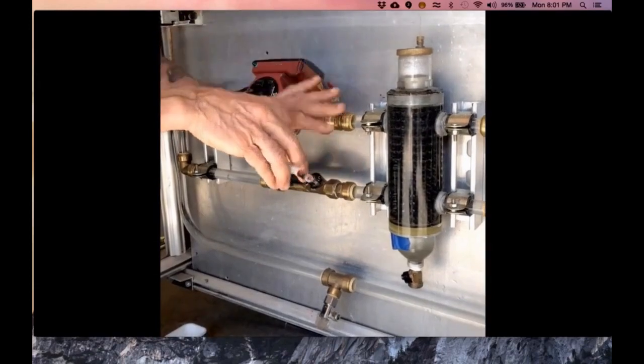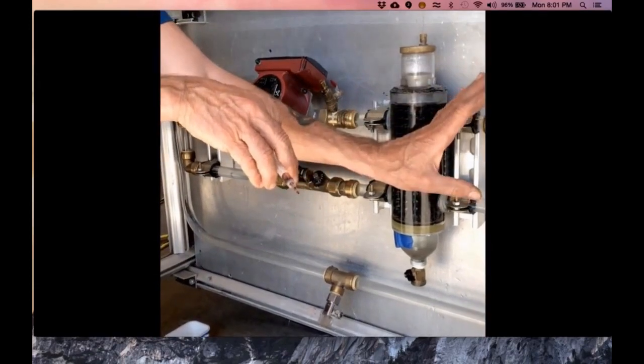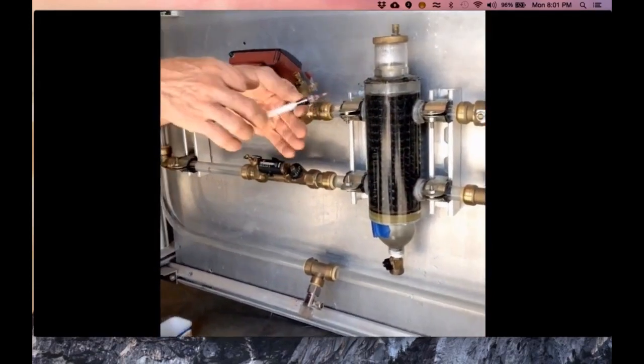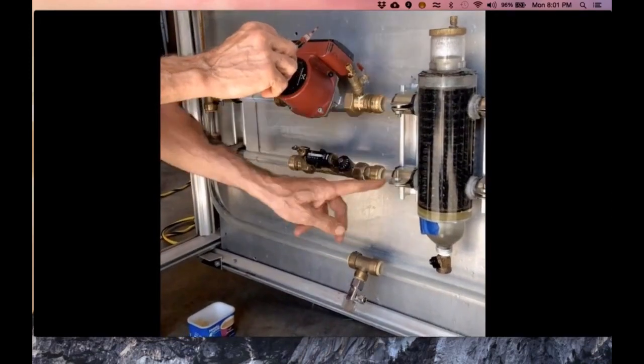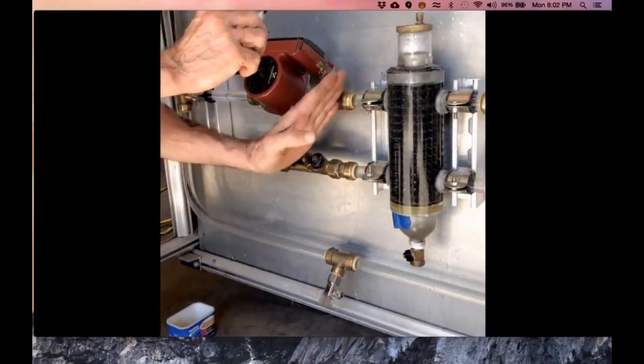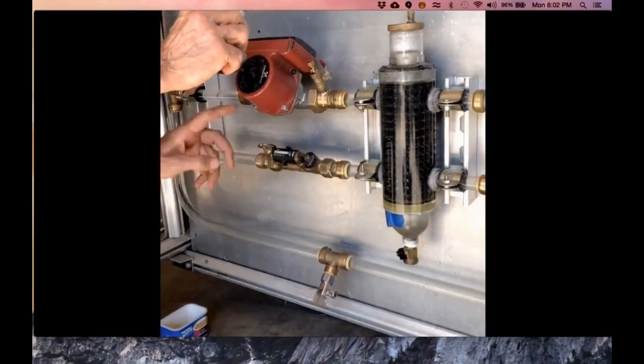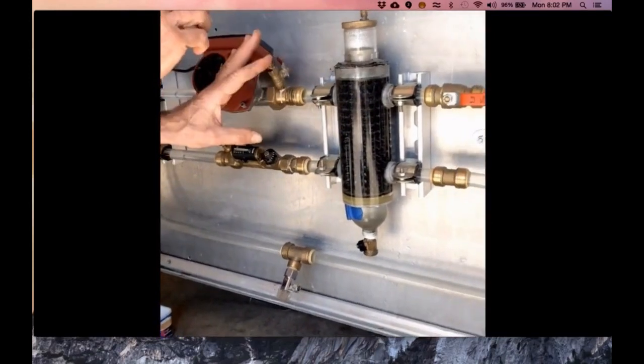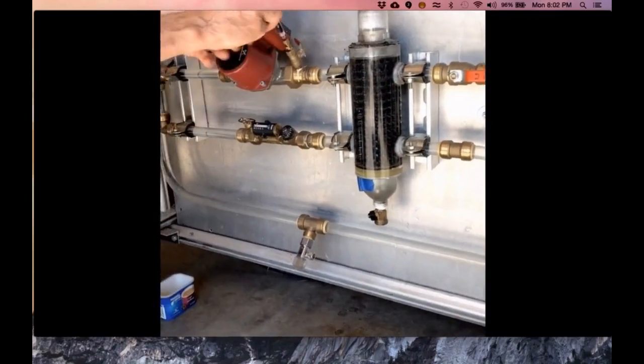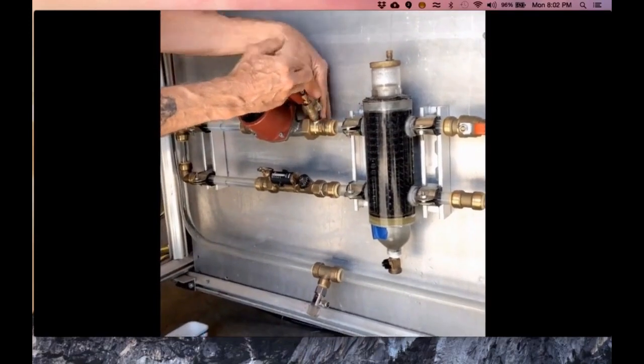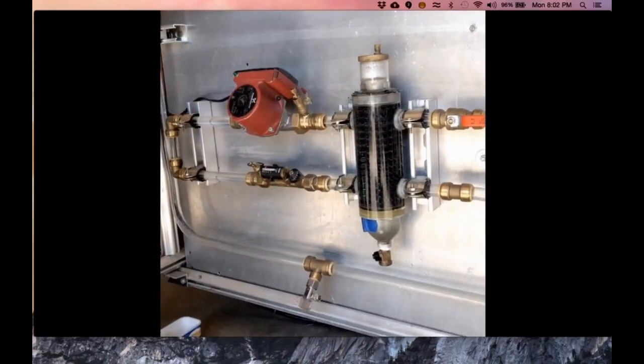All right, so first I'm going to run the secondary side without running the primary side, and I'm going to inject some red food coloring in here, and you're going to see it just circulate around. You might see a little bit push over here when I first kick the pump on from the force, but you're going to see that red just stay in this loop here when just this pump is running. So let me try this. Going to lose a little water probably doing this. Okay, I'm going to start up that circulator.